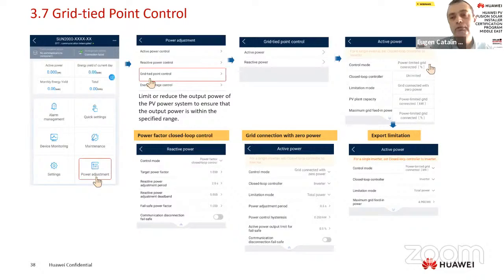How? It will produce only that value of consumption. If it can cover that value, it will work in limitation. If the inverter cannot cover that consumption, it will work unlimited and cover the power that it can, and the rest of the power will come from the grid.